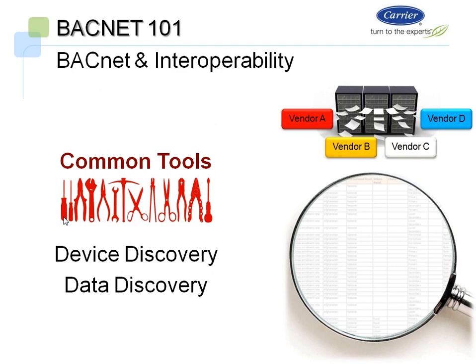There are a few other types of BACnet devices that help with integrating and providing interoperability. One of those is an auto-discover tool. When you plug in a different controller from a different manufacturer than yours, the auto-discover tool will automatically discover all the points that are talking via BACnet from that controller. This is huge, so you don't have to custom program all the points from a table you found or from a published points list. You can discover all the points being communicated from that controller at that time, reference each of them, and access each with a read or write property.